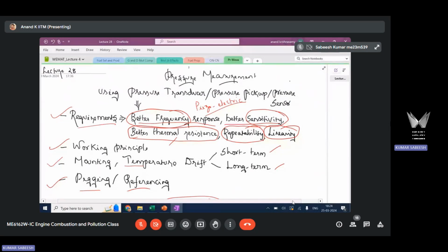Generally, sensors are calibrated with an equipment called a dead weight gauge, wherein you apply a known pressure and then measure the output from the sensor. Since the pressure value is known, the output value is correlated with the applied pressure. We need to have a linear correlation between these two, the input, which is pressure, and the output, which is an electric signal. If these two are linearly correlated, the problem is simpler. If it is non-linear, then you need to do calibration at multiple points in order to get the calibration constants, so you will end up with inaccuracies in the data if you have a non-linear correlation. To avoid that, it's better to have a linear correlation.